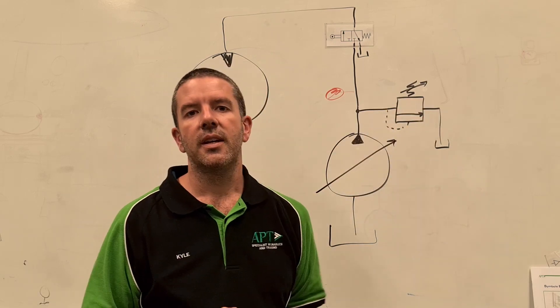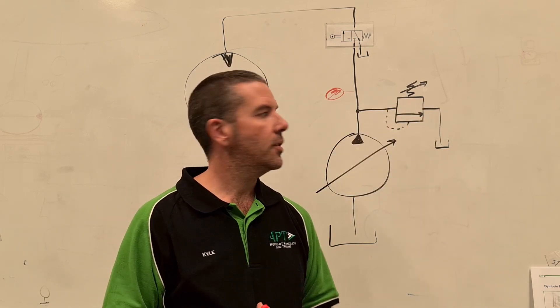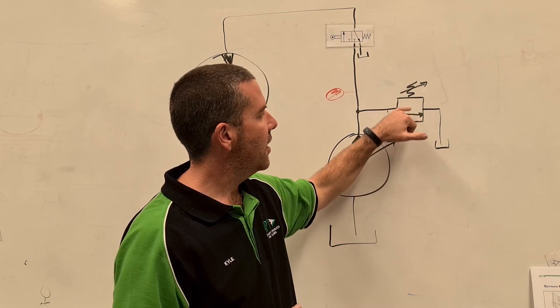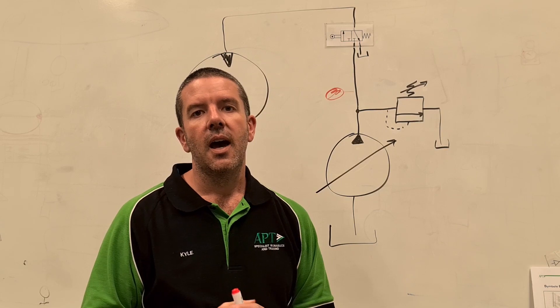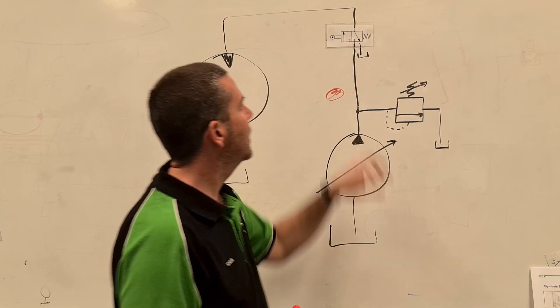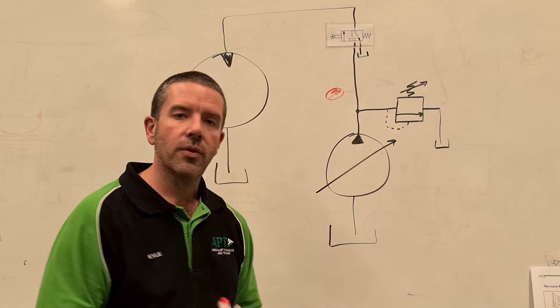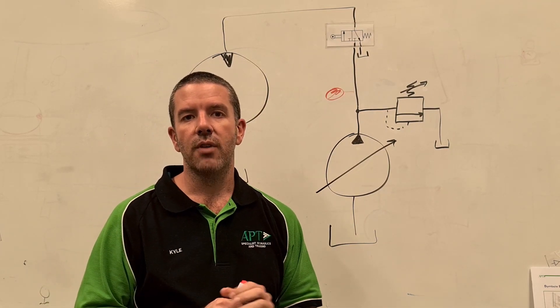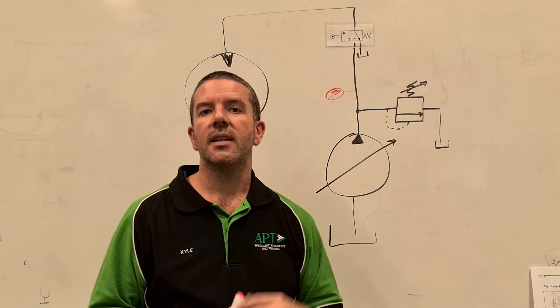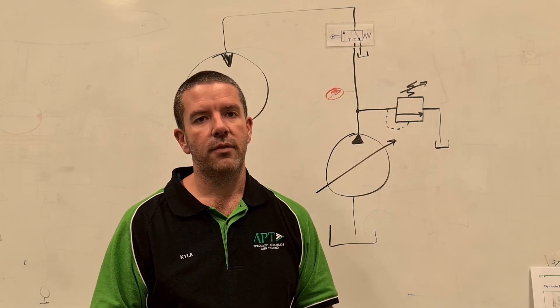A single box is a pressure or flow control of some sort. In this particular case, it's a normally closed valve because the arrow does not line up with the lines, so this is a relief valve or a pressure control valve of some sort. Two boxes or three boxes or more means a directional valve of some sort, and each box represents a particular state or a flow path through that valve.